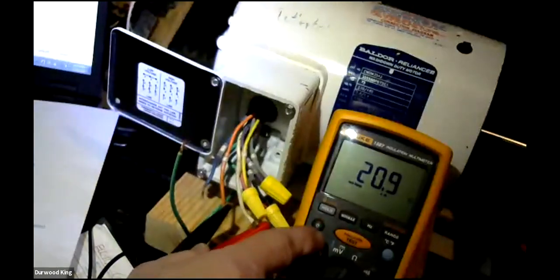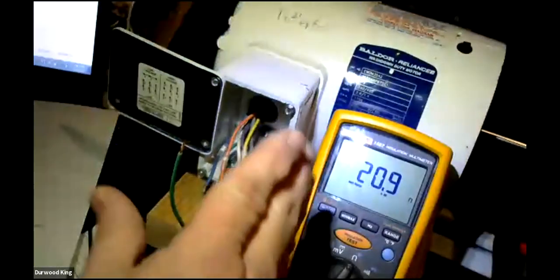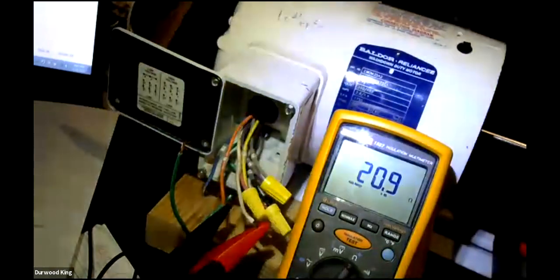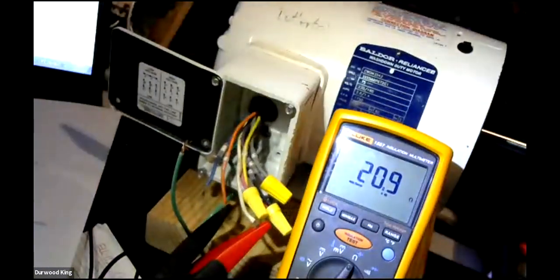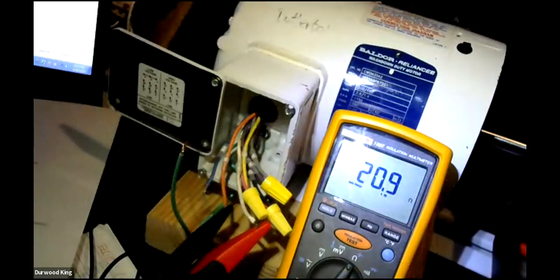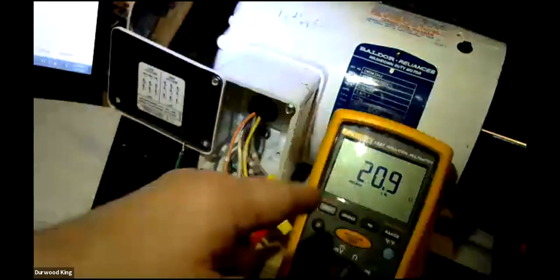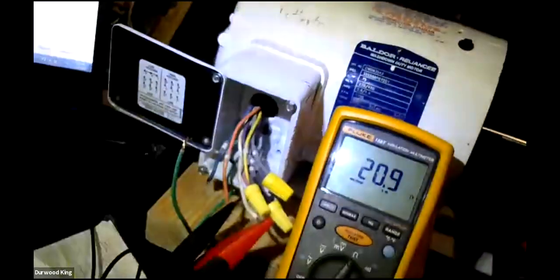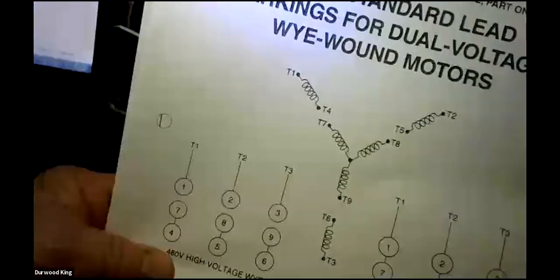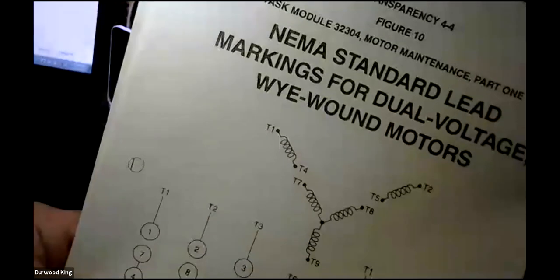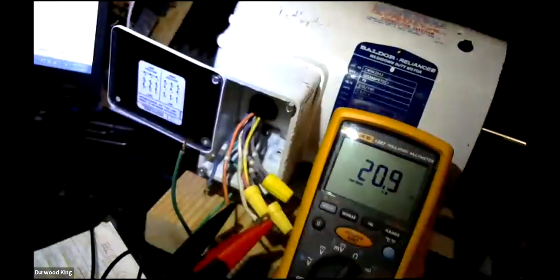That actually blew my mind. I had never seen that in my life. It was one of those moments that was a curveball to me, and I didn't know what I was looking at. It had me tripping there, guys. I swear it did, because it was a recirculating fan for an oven. It was real hot back there, about 115 degrees. I'm sweating bullets, and I didn't know what I was looking at. I said, man, how do I reason this out? I've got all the voltage there like I'm supposed to, but yet I've got amps and no amps. And the motor is sitting there crawling and groaning.